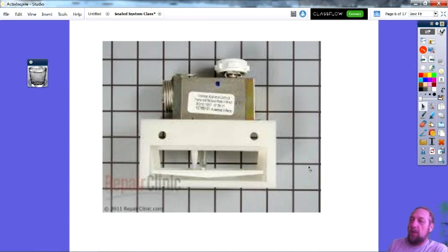So the customer calls you out and says, my freezer's cooling good, but my milk is spoiled, my refrigerator's not cooling. And so the first response is, well, either I have a defrost problem or a sealed system problem. So let me look at my evaporator. They look in the front of the unit, and if you look at the front of a side-by-side unit, you can see an opening and you can see the coils and see if ice is built up on those coils, and you don't see ice. And you're like, well, wait a minute. Do I have a sealed system problem? Well, what was it that the customer said was happening here?